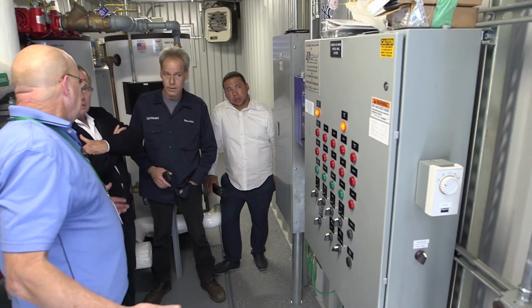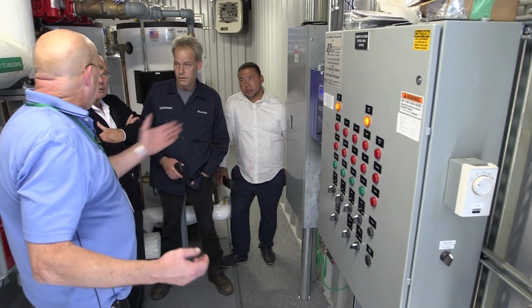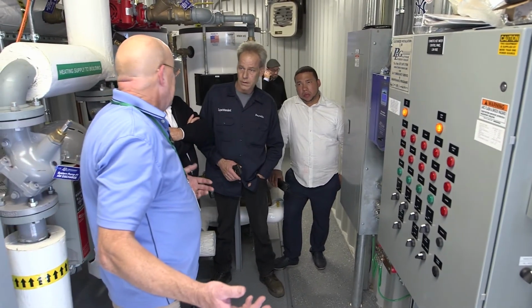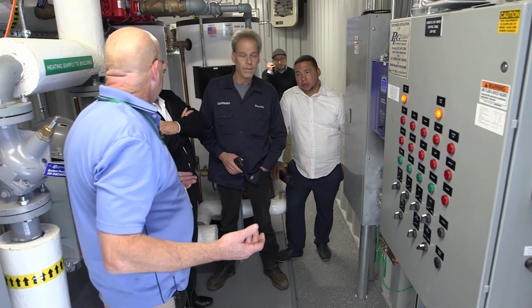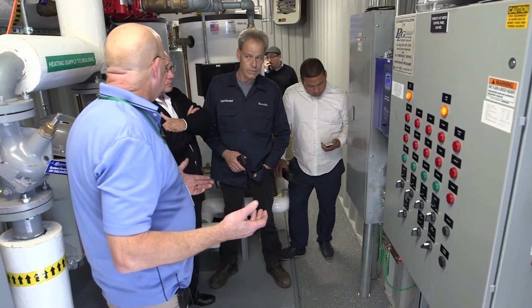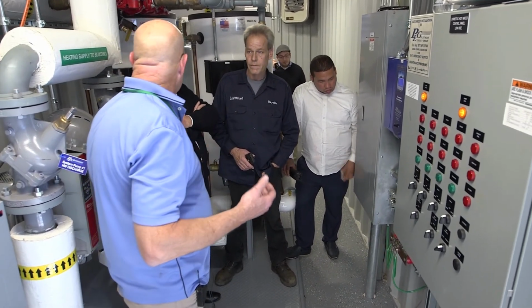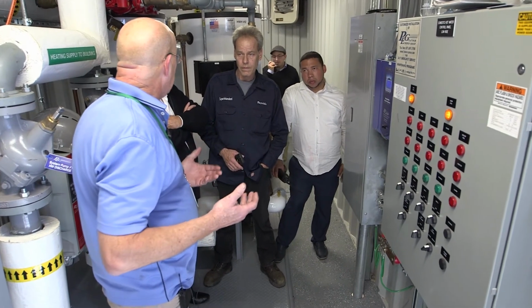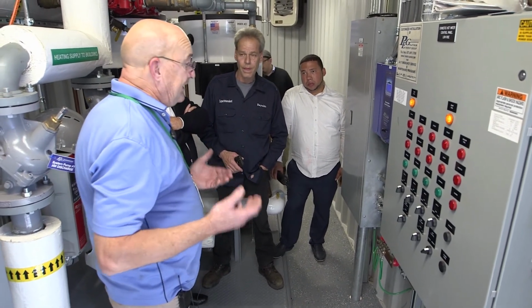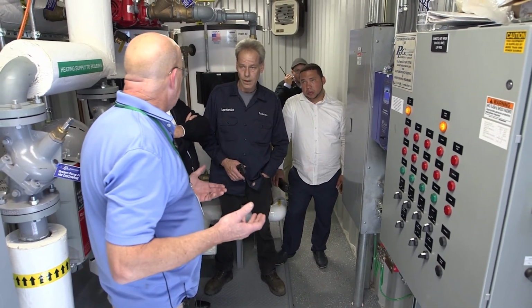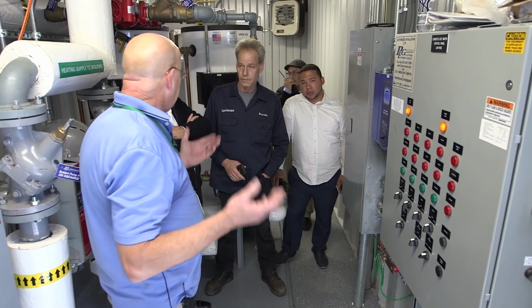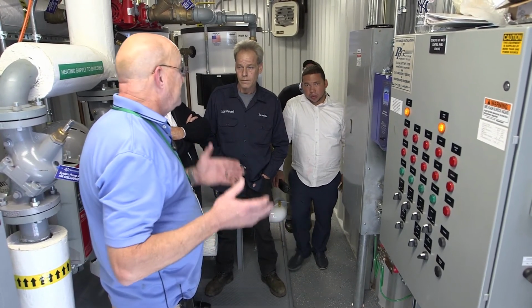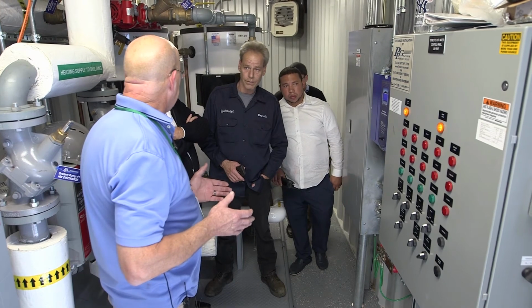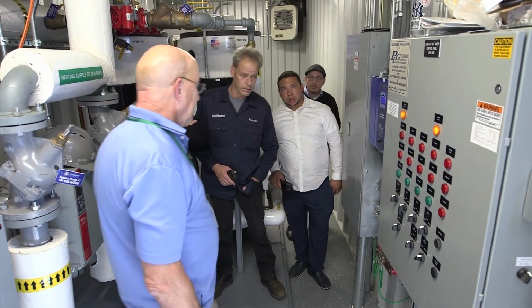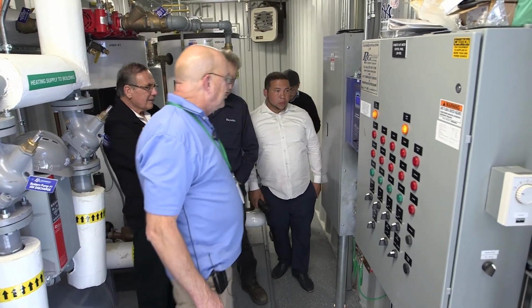You know what? My servicemen are human. Maybe they put it on bypass to test something and they forgot to put it back. You'll know they forgot to put it back, or you'll know you forgot to put it back, because you're getting a signal that the system's on bypass. At the end of the day, you'll get an alert: somebody has a system on bypass. It doesn't say you have to do anything about it. It's just telling you so that you can take the appropriate action. But normally this stays in the control side.